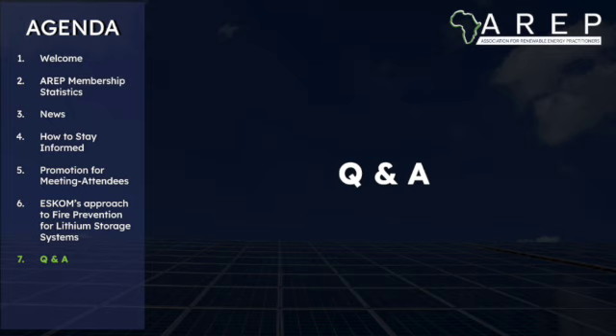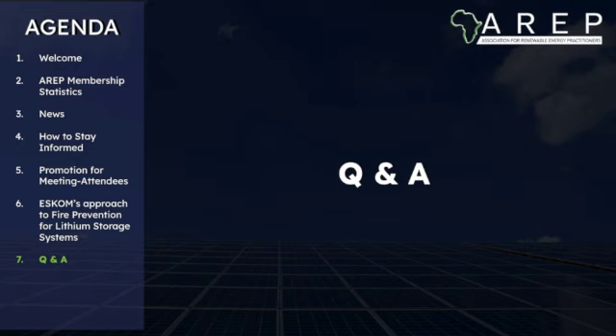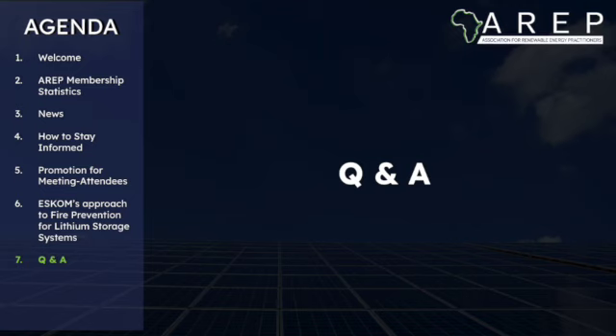I've seen in the market guys coming out with fire extinguishers specifically for lithium ion batteries, filled with some kind of vermiculite type substance that they say moves into the battery chemicals. I don't know how much those cost, but you get guys claiming to have fire extinguishers with a liquid inside that can cover lithium ion batteries. Just be careful - make sure if you go for anything like that, you have a certification and a test report. Don't promote something just because the guy says so; have proof to back it up.